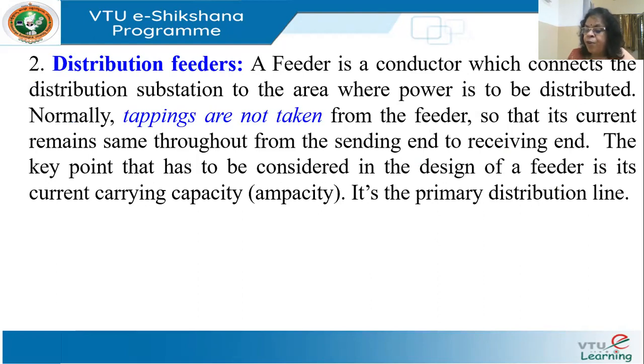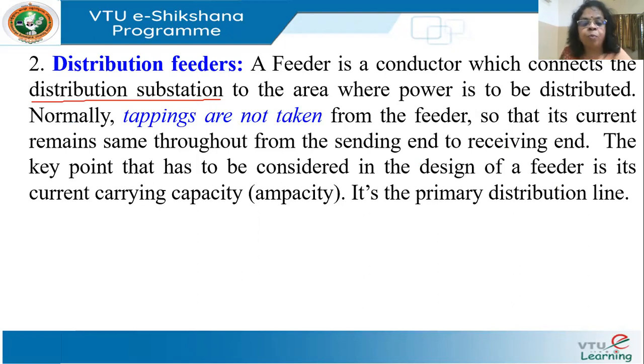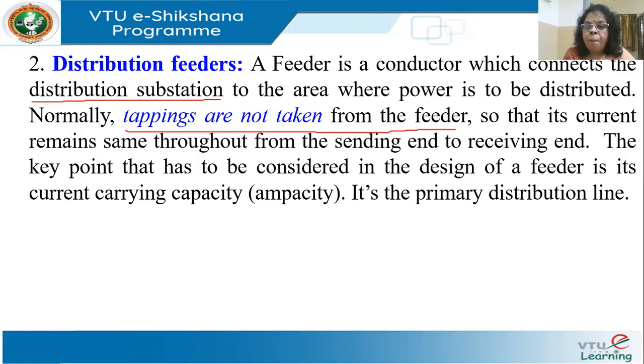The next component is the distribution feeder — a conductor connecting the distribution substation to the area where power is to be distributed. Tappings are not taken from the feeder in between, so the current remains the same throughout from the sending end to the receiving end. The main design parameter for a feeder is its current carrying capacity, called ampacity. These conductors are the primary distribution lines.